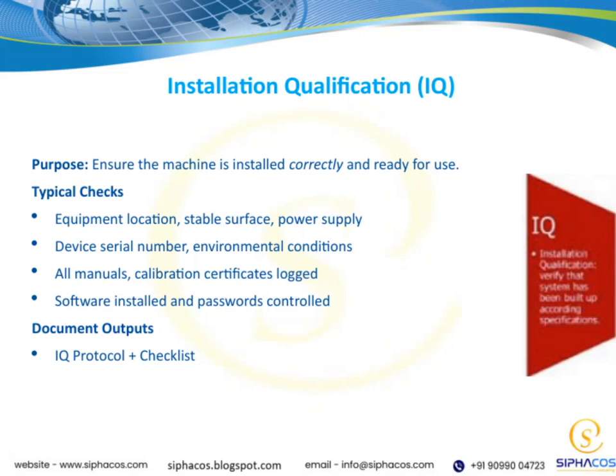Now, let's talk about installation qualification, or IQ for short. The main goal here is to make sure that the machine is installed correctly and is fully prepared for use. This step is critical because proper installation sets the foundation for the entire qualification process. When performing IQ, there are several typical checks to keep in mind. First, we want to verify the equipment's location, ensuring it's placed on a stable surface in a suitable environment.